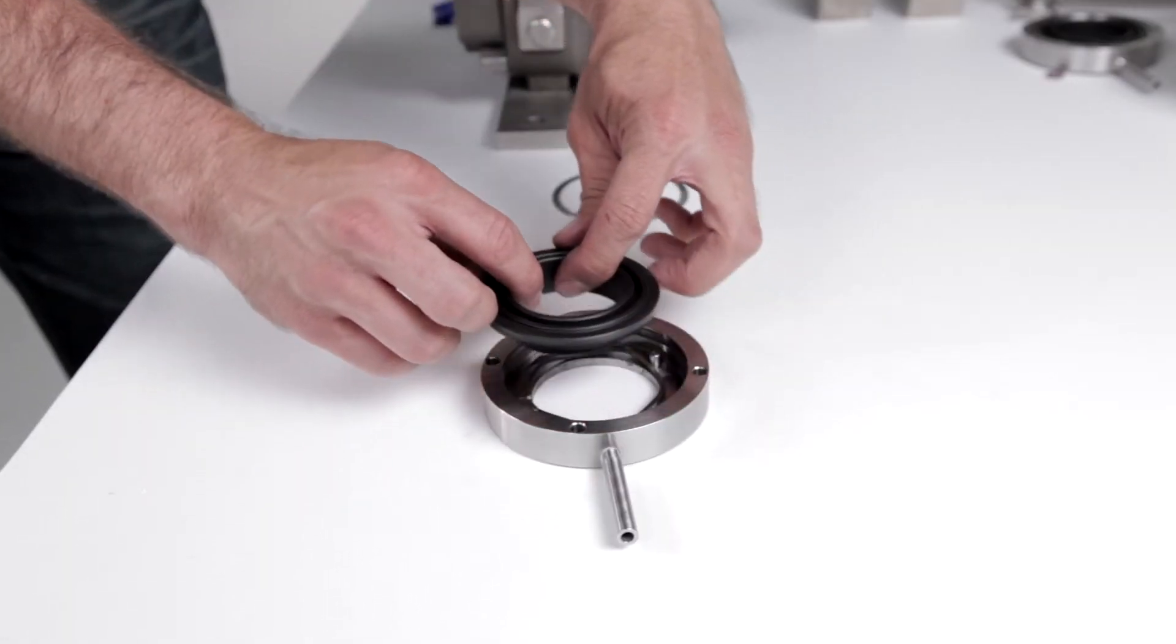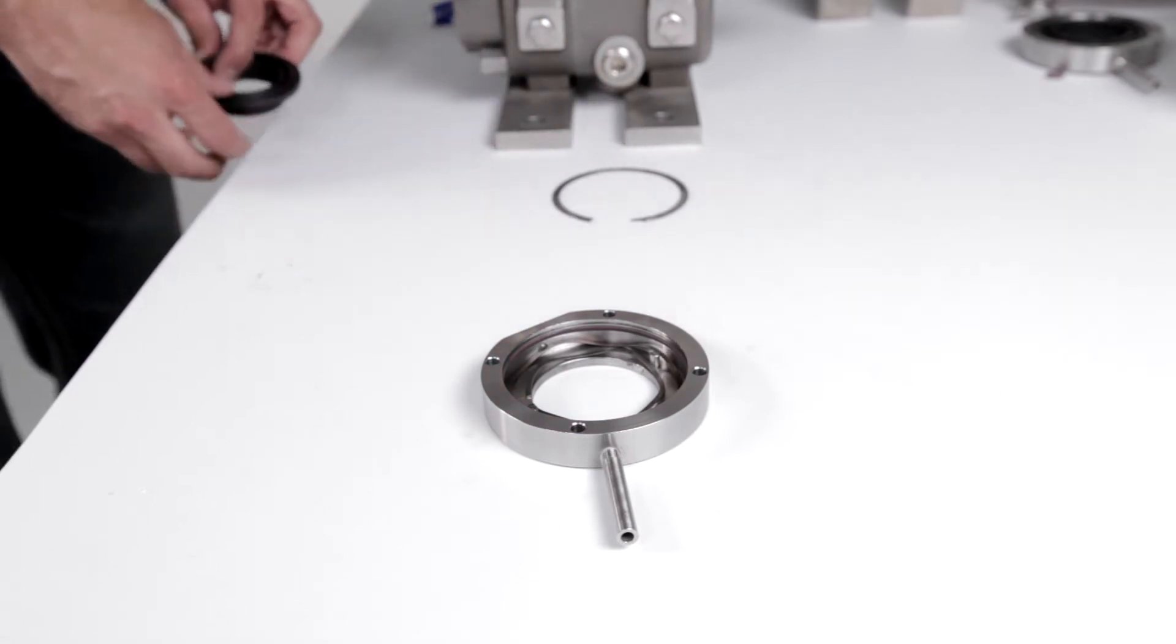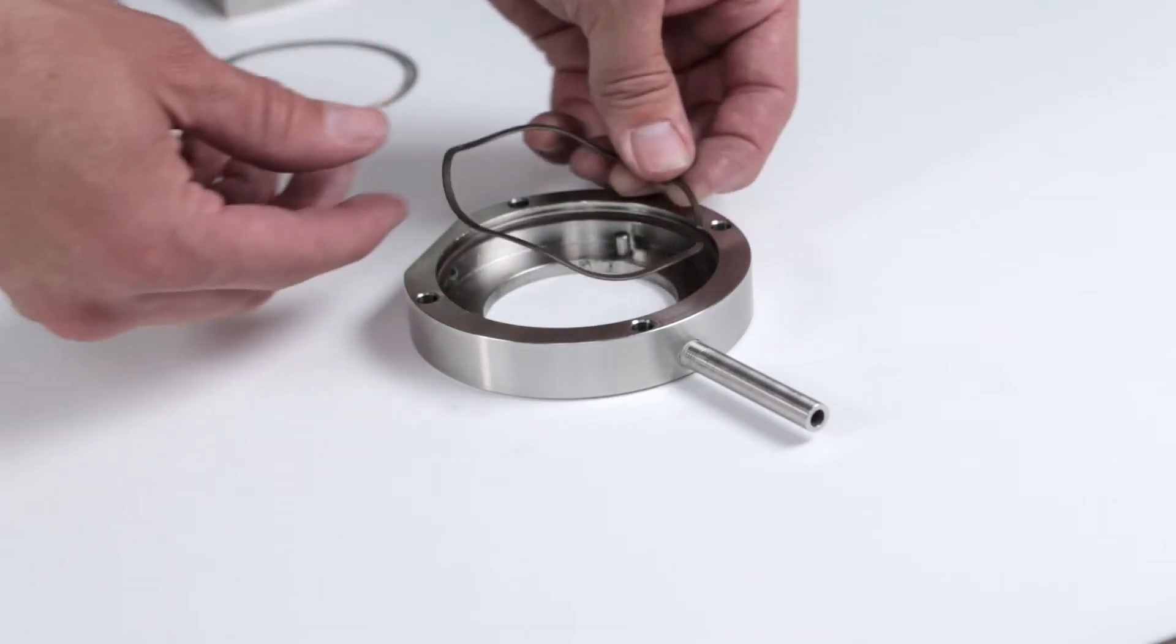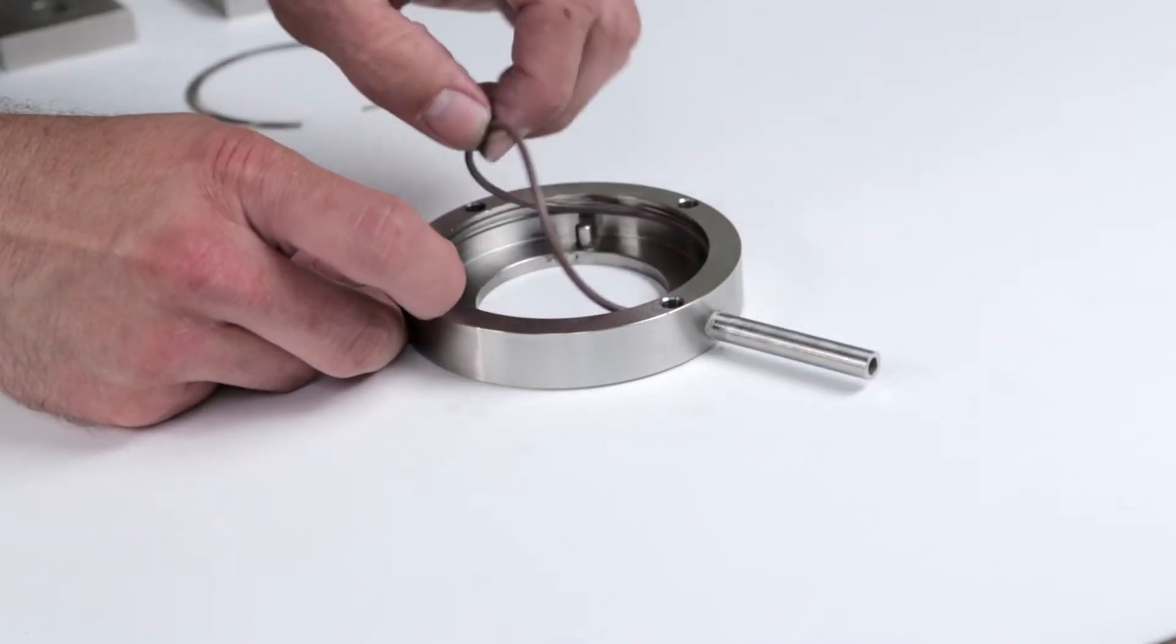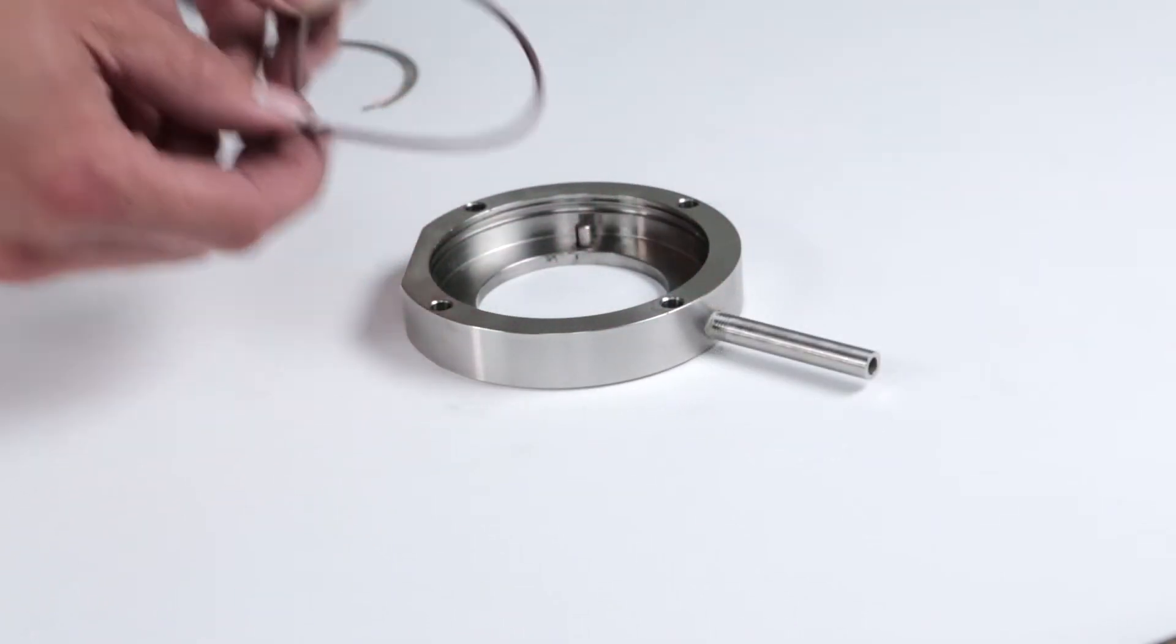Use your fingers to gently press the two seal elements out of the seal housing. Remove the double and single seal springs. Remove the outer seal o-ring. Discard all elements of the seal except the cartridge housing and pins. For larger models, remove the seal cartridge o-rings and discard. The seal housing should be cleaned to prepare it for reassembly.